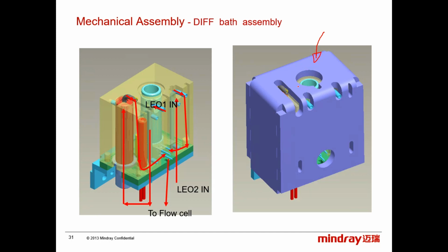So this has its own resistance inside to preheat the bath, because the temperature is very important for the reaction, for the lysing reaction. If the temperature is too high, it will affect the internal complexity of the cells. If it is too low, then of course it will delay the lysing process. As we know, the lysis sequence is limited in time, so by the time we send the sample to the flow cell, maybe some of the RBCs are not lysed entirely, and we will get a lot of ghosts. So this is the LEO1 injection, LEO2 in. Of course, here it will not be injected directly. It has a longer path to allow it to preheat.